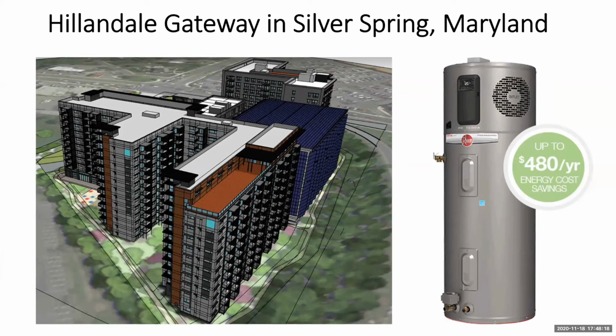There's a cold climate HVAC system for the hallways so that we don't chill the hallways. We're delivering heat very efficiently at like a COP of 3 to 4 in the wintertime. And then the water heaters are able to capture that heat at a very similar efficiency, like 3 to 4, because it's 70 degrees Fahrenheit in the hallway, maybe 65. And that's perfect for a heat pump water heater. It loves that temperature. So we have a very efficient system, and it's not expensive to build.